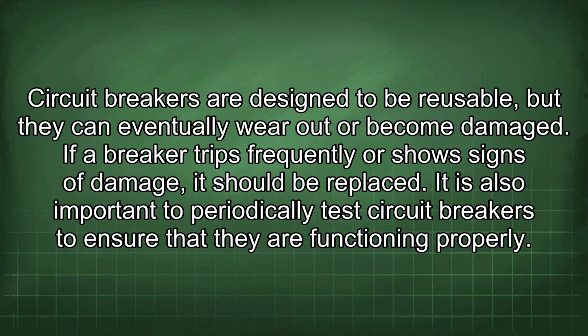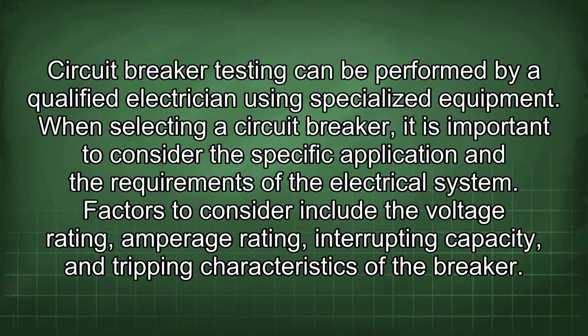Circuit breakers are designed to be reusable, but they can eventually wear out or become damaged. If a breaker trips frequently or shows signs of damage, it should be replaced. It is also important to periodically test circuit breakers to ensure that they are functioning properly. Circuit breaker testing can be performed by a qualified electrician using specialized equipment.